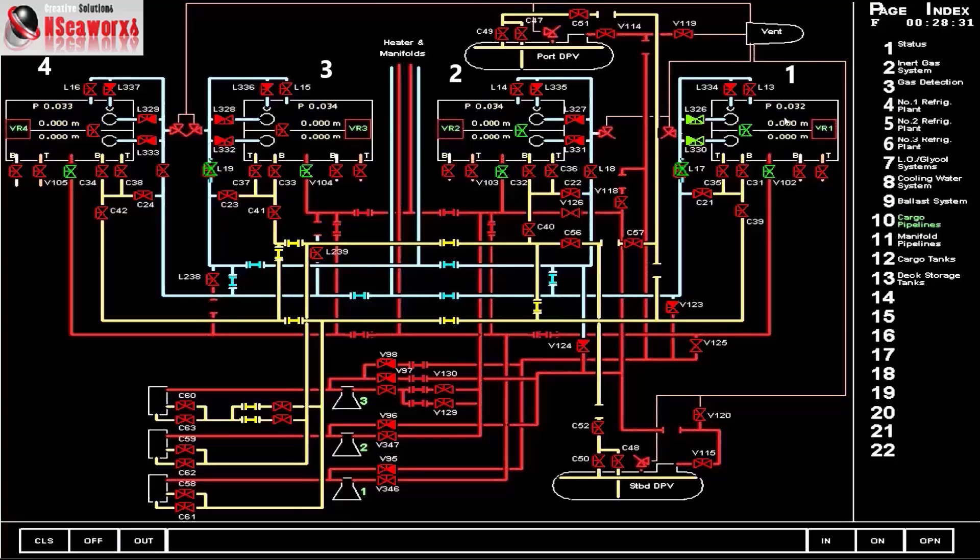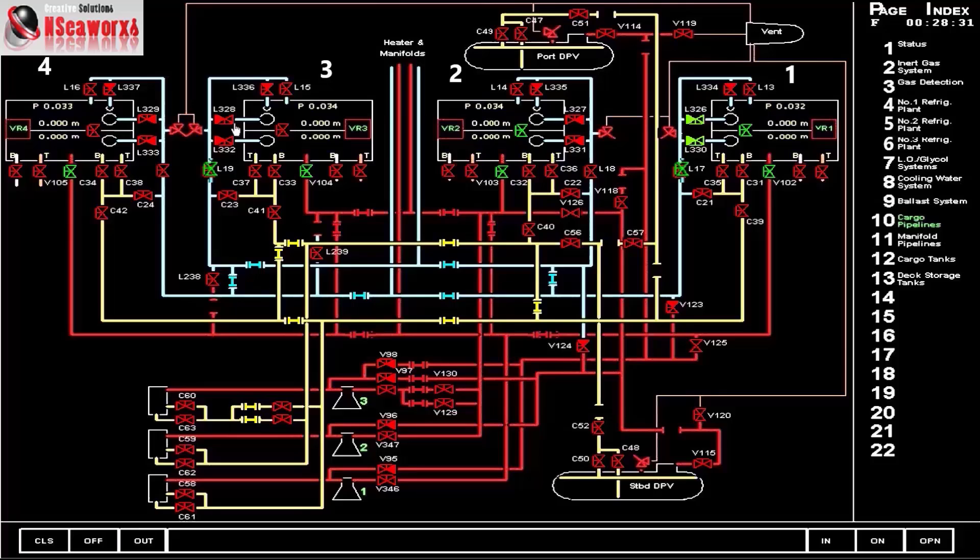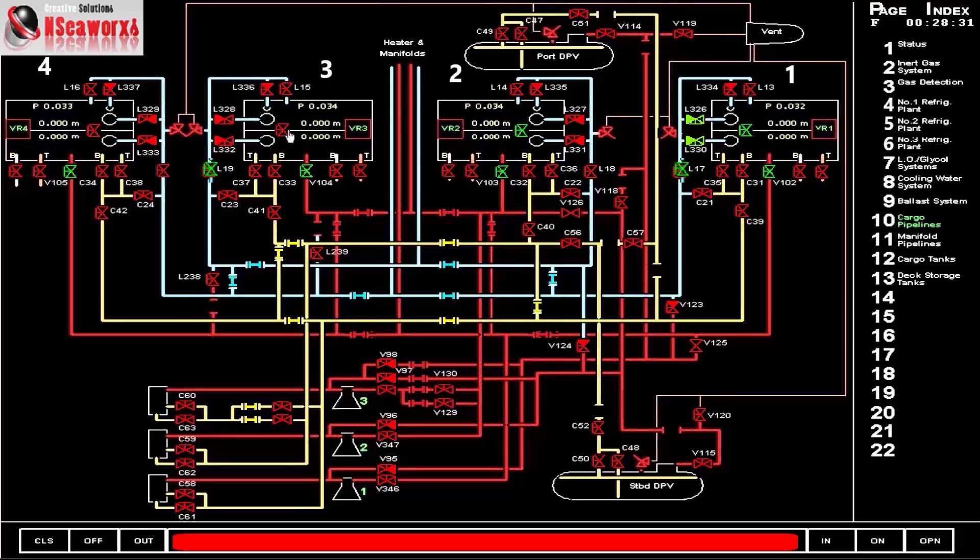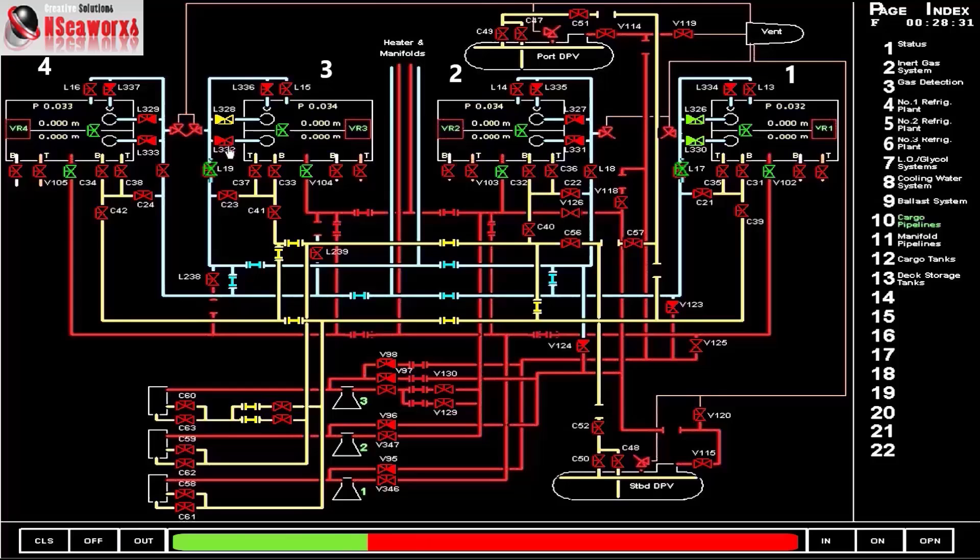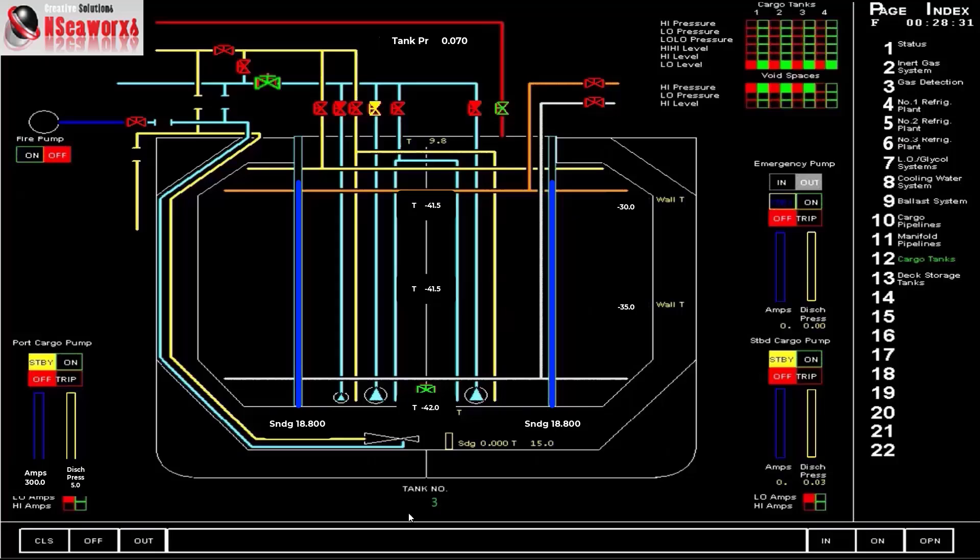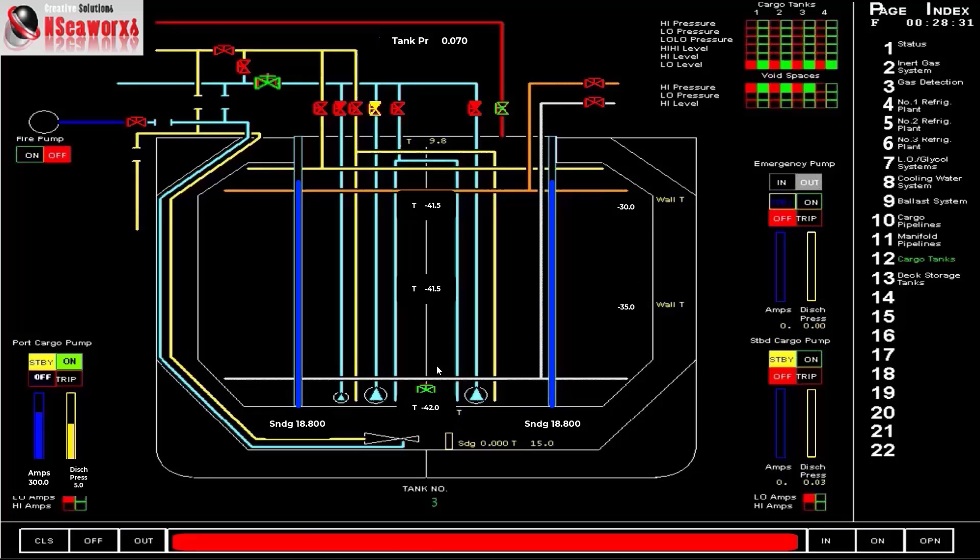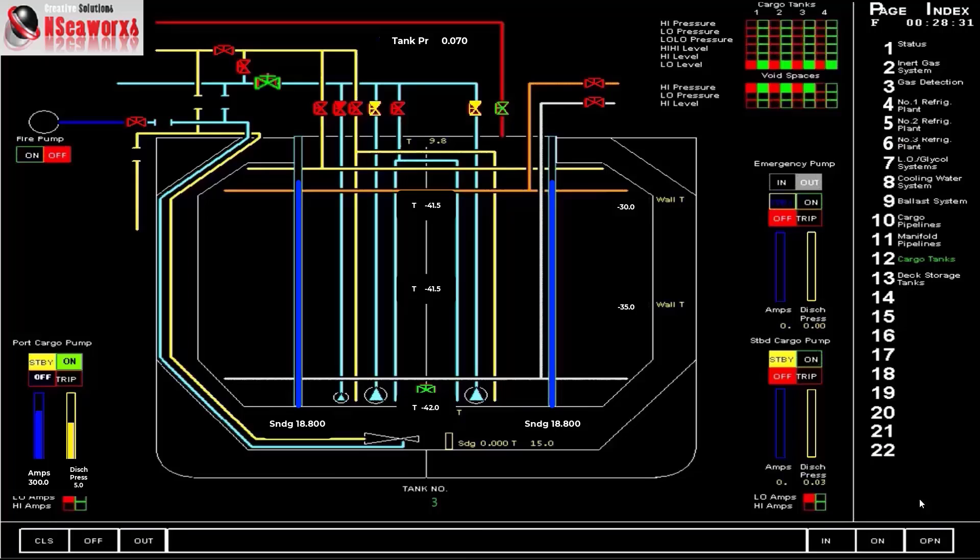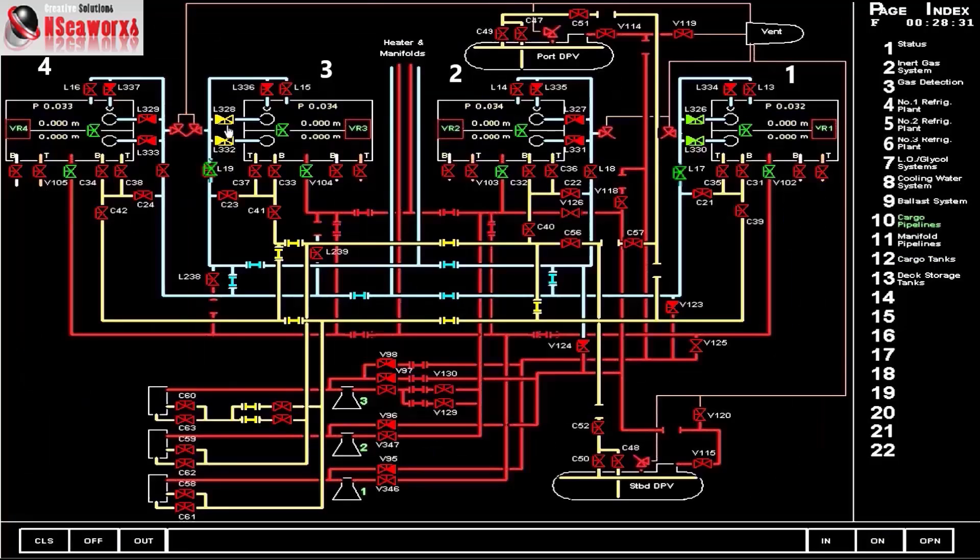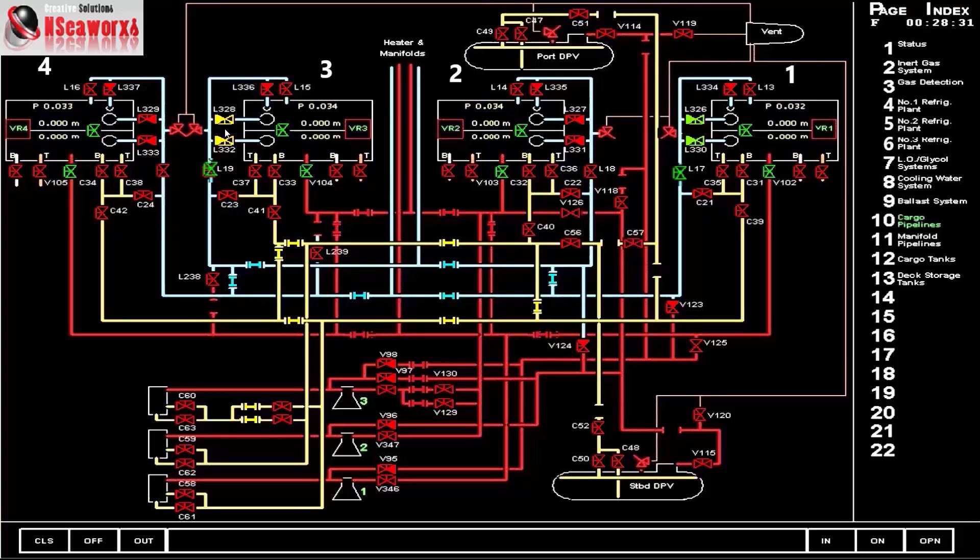Say for example, you started one and you might start with number three as well. So make sure that the leveling valves are open as well. So it should be open. And let's just say we start as well cargo pump number one for port side for number three. So this is number three. And then I'll start number one port side, and then likewise I'll start starboard side. So slowly I am now increasing the discharge pressure. If you go to cargo pipelines, you can see here that the discharge valves are throttled so that I could control the discharge pressure. And eventually I will be able to discharge all four cargo tanks simultaneously.